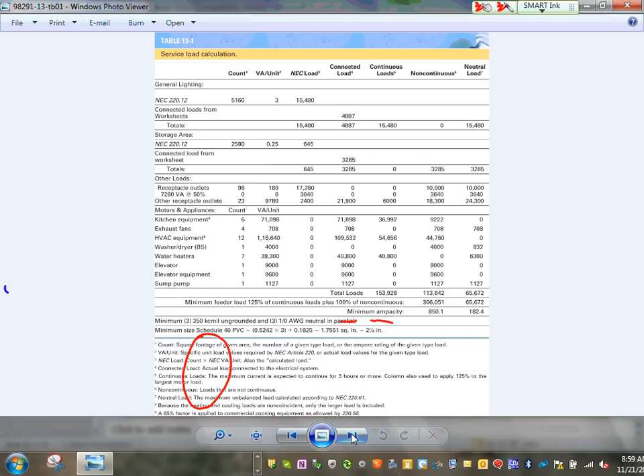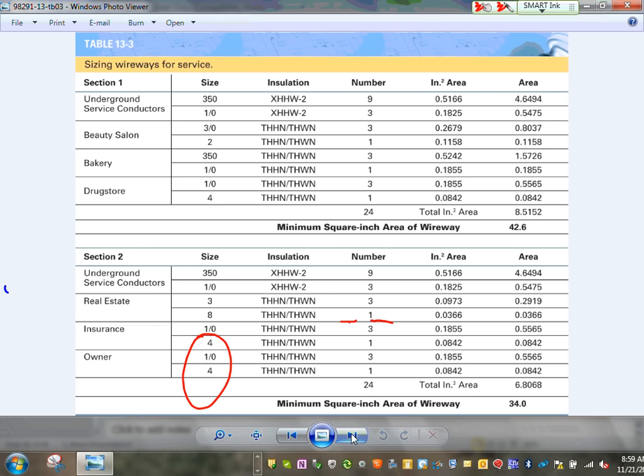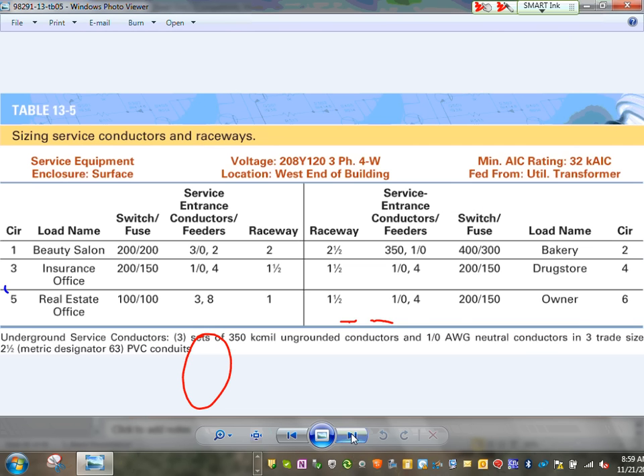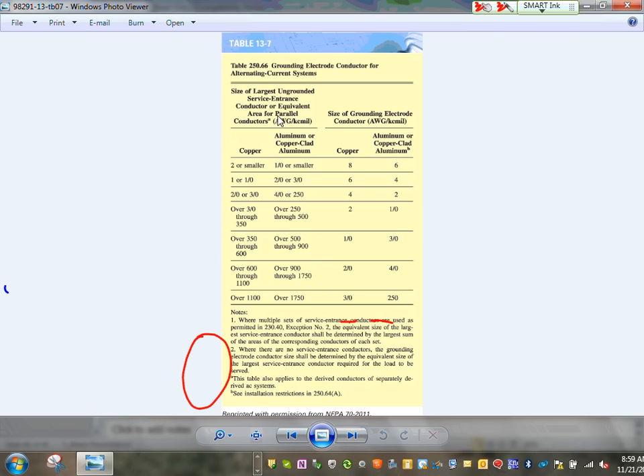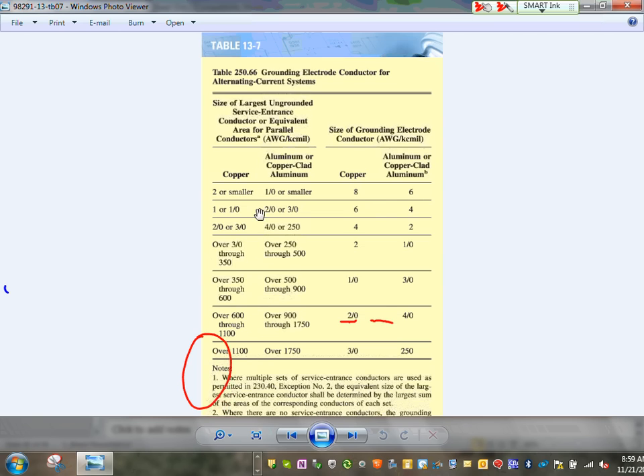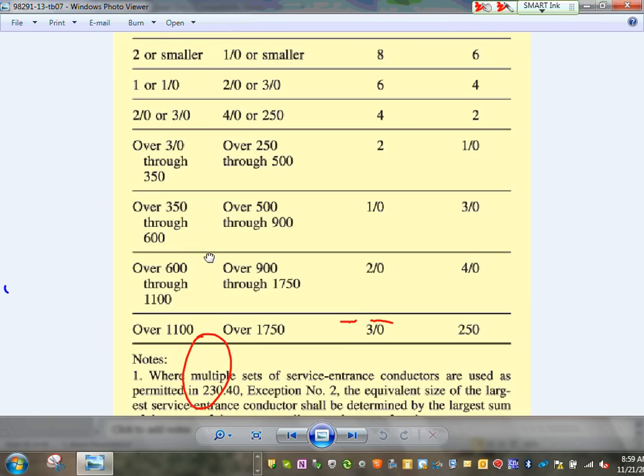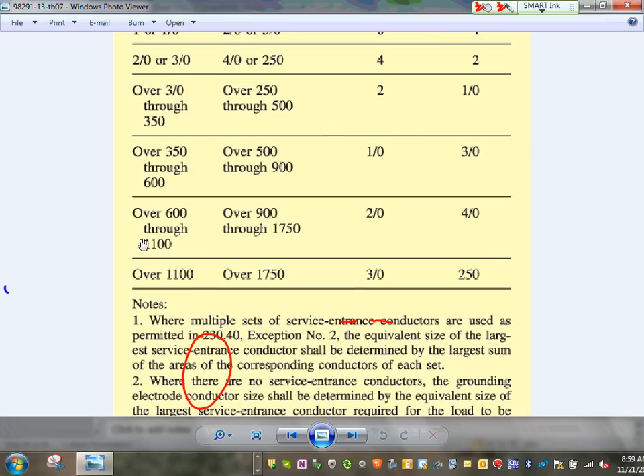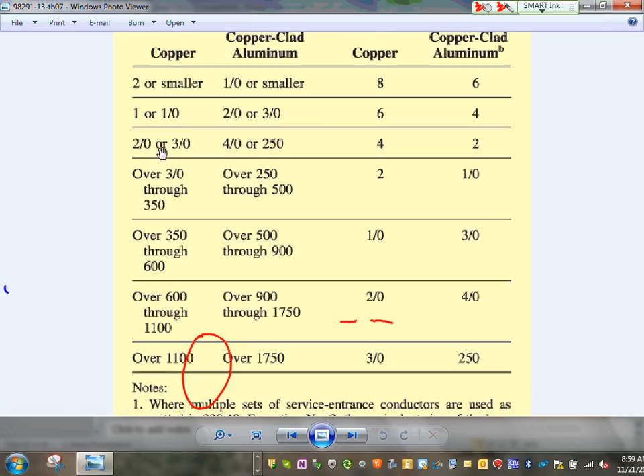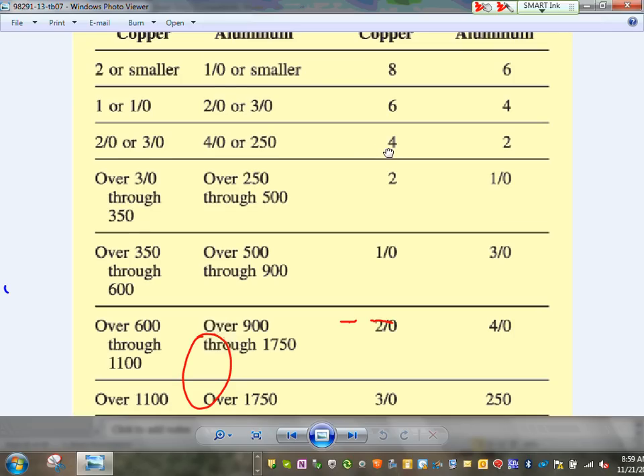This is just the calculation that they did for their service, and they sized the service conductors. You guys have done that intensively with your friend Chad. This is 250.66, guys. So if my service conductors are 700, for example, then my grounding electrode conductor, Adam, is 2/0, and my main bonding jumper is 2/0. So if my service conductors are 3/0, then my grounding conductor is number 4, and my system bonding jumper, main bonding jumper and supply side bonding jumper are number 4.